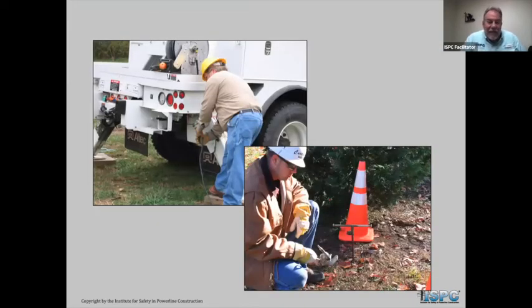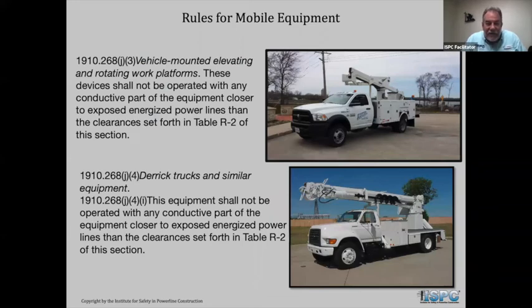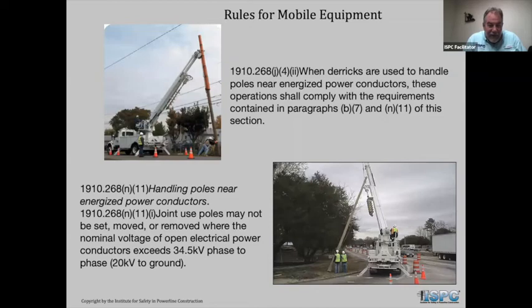Grounding trucks. Most of our communication guys do not ground their trucks, and it's because a lot of times they drive while lashing cable and things like that. But we talk a lot about what some of the hazards would be grounding the truck, going to a ground rod, or going to a down ground wire that's coming down a pole. Creates another risk to the employee. 1910.268(j) talks about rules for mobile equipment. So we go through some of the bucket rules and some of the derrick trucks, the minimum approach distances, talk a little bit about that while you're in the bucket, things like that.